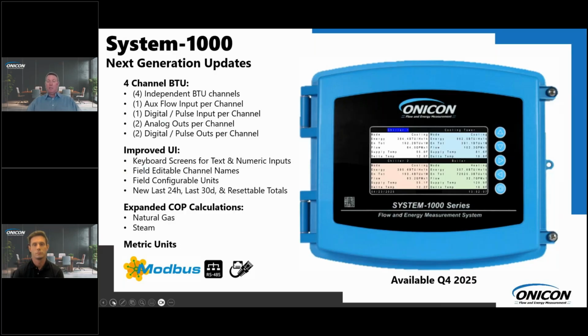We also dug into the user interface for the System 1000 based on some feedback we've gotten, and we've installed new keyboard screens that will help you with text and numeric inputs when you're working on the device from the keypad. We've added field editable channel names in case you want to repurpose some of the channels of your System 1000. You'll be able to do it there without the use of a laptop. You'll also be able to field configure the units on the display of your System 1000 for however you want to see them for your mechanical room, and you'll be able to do that through the keypad on the front of the System 1000.